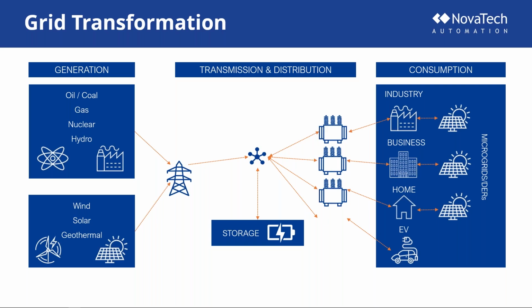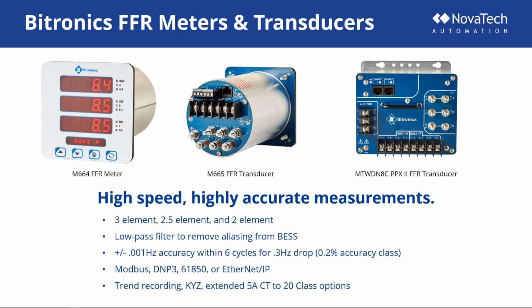Because that time is so short, you need to be able to measure that accurately and quickly, within a few cycles. So how do you do that? You do that with automation. And one of the ways you can do that is with a fast frequency meter. So we're kind of bringing this in the digital world. Fast frequency meters are going to be needed. We've developed some firmware for our meters that allows us to have front-end filtering to mitigate aliasing effects of battery storage systems. And we can actually reach 1 millihertz accuracy within 6 cycles. This fast measurement capability is a fraction of the response time of a traditional meter, and that allows fast frequency response of 15 to 20 cycles.